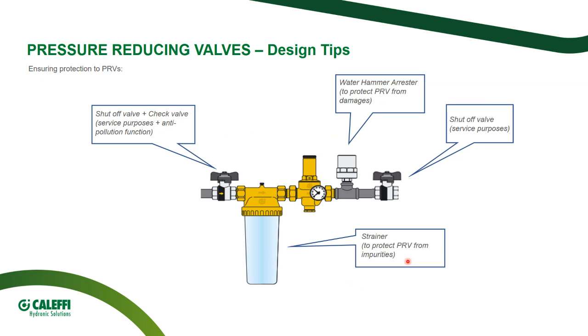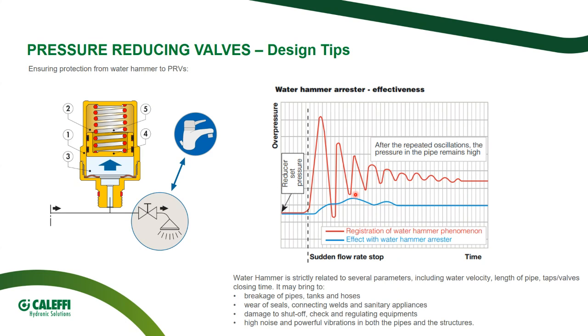As we speak about pressure reducing valves, we cannot avoid, and then we are really finished with the presentation, equipping the system with some devices in order to ensure the PRV has the right protection. So, of course, strainers in order to control water quality and avoid impurities sticking, not only on the PRV but in any other device of the system. Provide the system with shut-off devices in order to be quick and effective in maintenance. And then consider, in medium-size systems, the installation of water hammer arresters. Water hammer arresters prevent damage, not just to the PRV, but to the calorifier, heat exchanger, everything in the system.